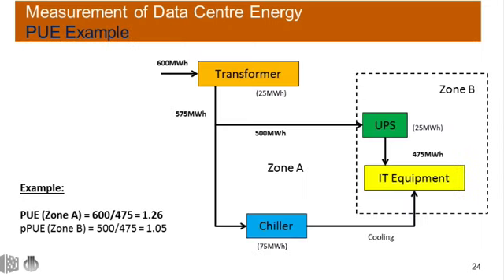So the measurement of data center energy, PUE and partial PUE, is fairly straightforward. So PUE is the total facility energy divided by the IT equipment energy. The total facility energy would include UPS, switchgear, transformers, cooling infrastructure such as input power to chillers, CRAC units, AHUs, and some of the more miscellaneous systems such as lighting. Whereas the IT equipment energy purely focuses on the IT load, so compute, storage, and network equipment. Partial PUE is fundamentally the same as the above, but it considers the components within a defined boundary rather than the entire facility. And I can explain that in a little bit more detail on the following slide.